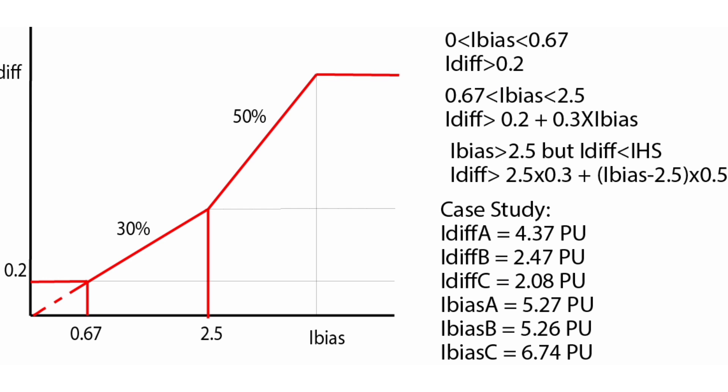The initial setting given for differential current is 0.2 per unit. Beyond that, a 30% slope starts, which meets the origin and continues up to 2.5 per unit of bias current. Beyond this bias current, a 50% slope for the higher region starts. This is the characteristics of the differential relay for the MICOM P648 relay.